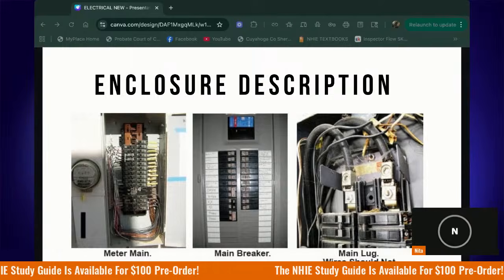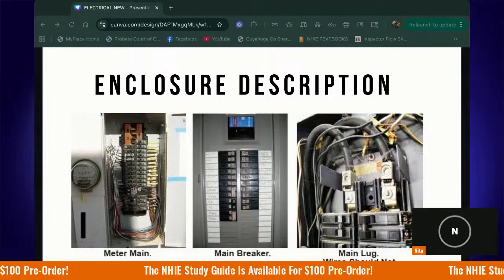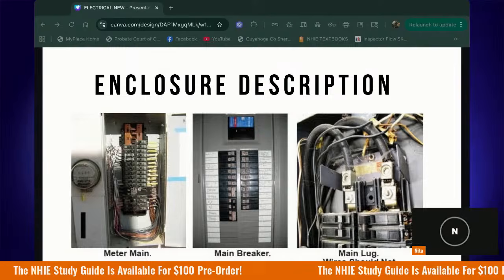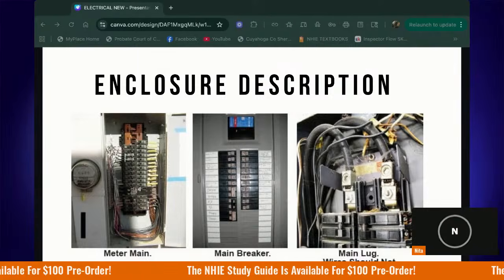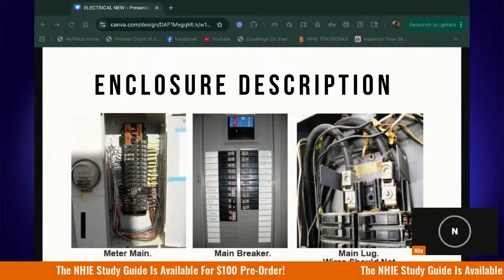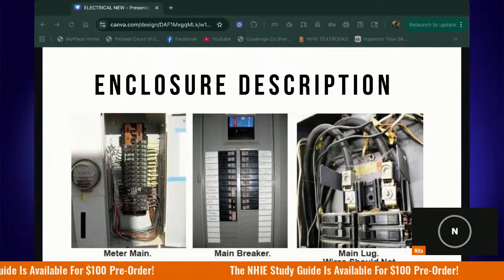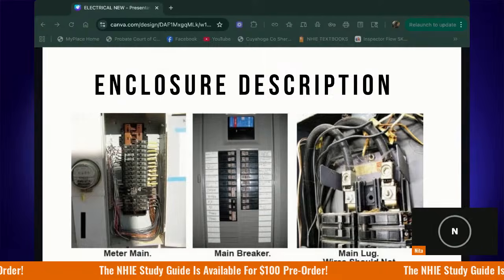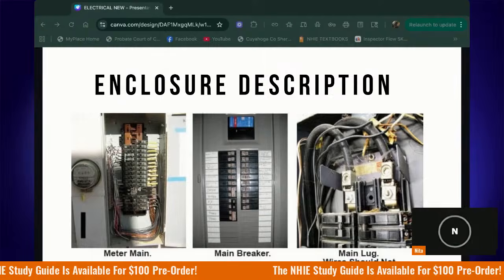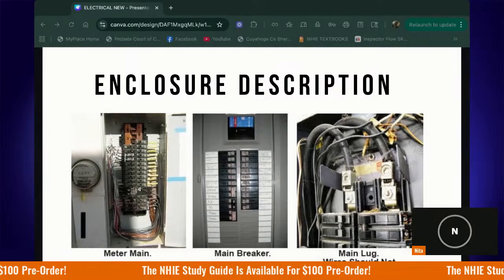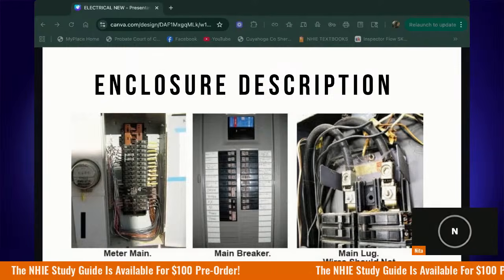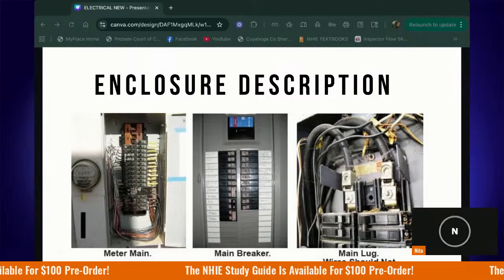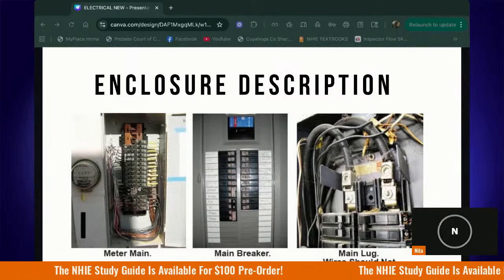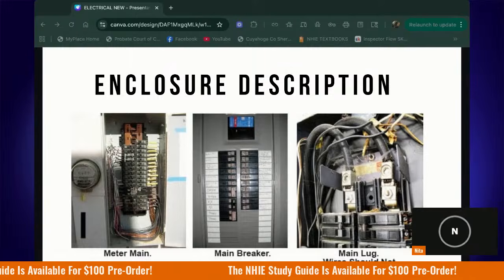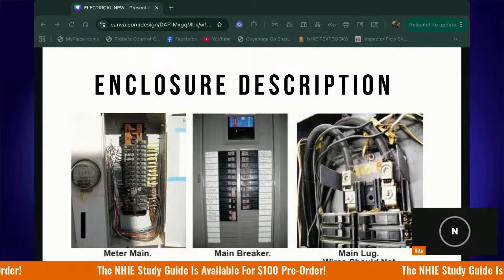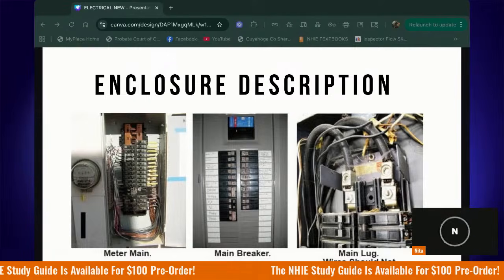So most residential enclosures, like I said, are made from galvanized metal. You can have non-metallic enclosures, like fiberglass and stuff like that, that are approved for indoor and also damp areas. Because, to Miss Sims' point, you can have outdoor enclosures. They have to be rated for that, but they can be outdoors. Your enclosures, whether in or out, can be installed directly to the wall, or they can be installed on top of a wall surface. This is like what it's like when you have a basement.